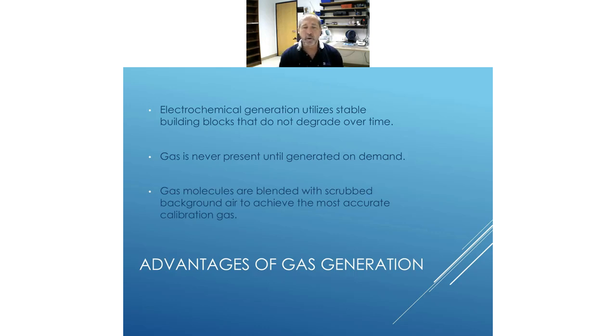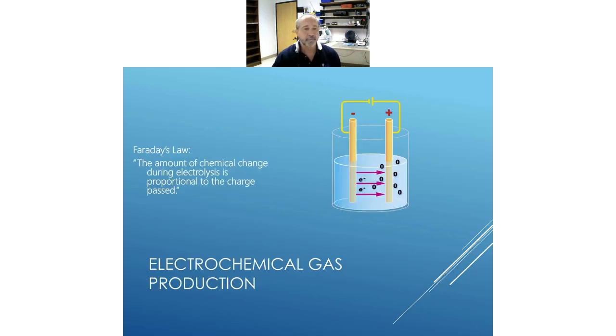So that gas isn't stored, and as we generate these gases on demand, the molecules of the gas that are generated are then blended with a scrubbed background air, and you get a better calibration than you would even if there was a cylinder of the gas you wanted. The basics of electrochemical generation are as old as time. With a galvanic cell, there's a proportionality: if you want to generate a gas, you apply a certain amount of energy to a cell, a galvanic cell like we're showing here on the slide, and you get an X amount of molecules of the gas that you're trying to generate.